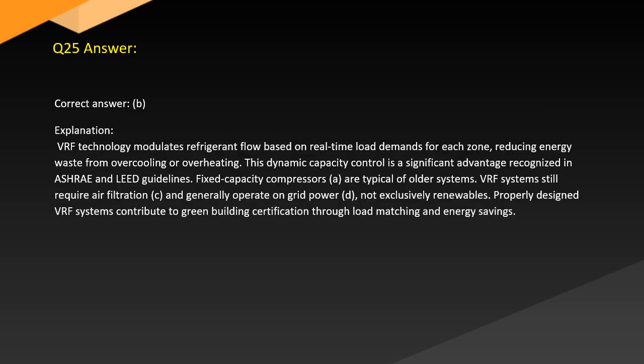Answer. Correct answer: B. Explanation. VRF technology modulates refrigerant flow based on real-time load demands for each zone, reducing energy waste from overcooling or overheating. This dynamic capacity control is a significant advantage recognized in ASHRAE and LEED guidelines. A. Fixed capacity compressors are typical of older systems. C. VRF systems still require air filtration and generally operate on grid power. D. Exclusively renewables is incorrect. Properly designed VRF systems contribute to green building certification through load matching and energy savings.